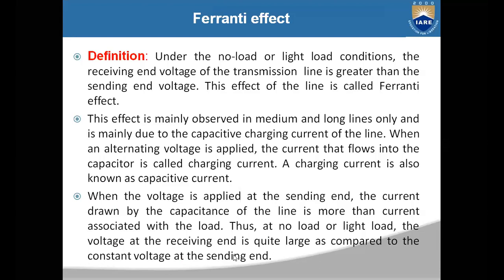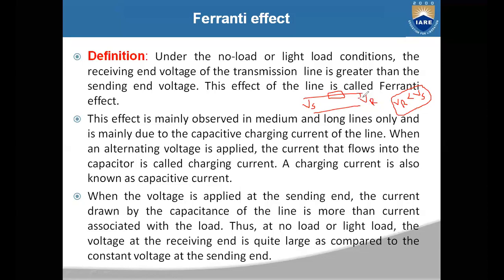Generally, if you observe a transmission line, you will have the sending end voltage on one side and the receiving end voltage at the load. The transmission line has a series impedance consisting of resistance as well as reactance. Usually VR will be less than VS under full load condition. But in some cases, the receiving end voltage will be greater than the sending end voltage — that effect is called the Ferranti effect.